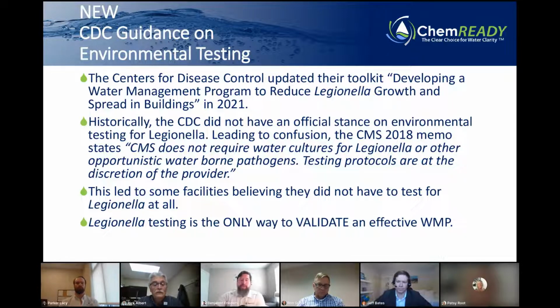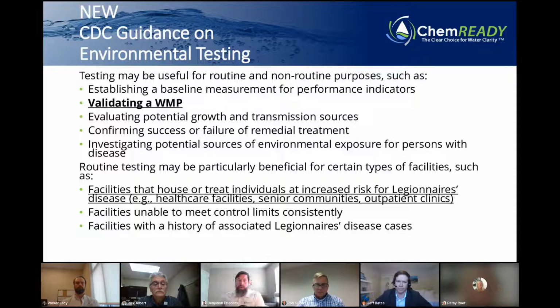So what else did the CDC update in 2021? This is straight from the CDC's website, and the updated guidance for 2021 says that testing may be useful for routine and non-routine purposes, such as: 1, establishing a baseline for measurement of performance indicators, and 2, validating a water management plan. So the big update that healthcare facility owners and managers need to understand is that the CDC's official stance now is that routine Legionella testing is essential in validating a water management plan.